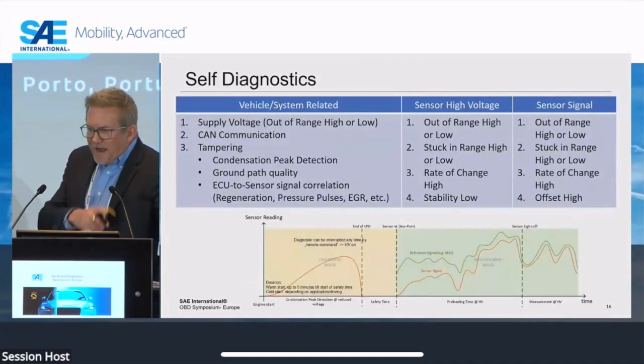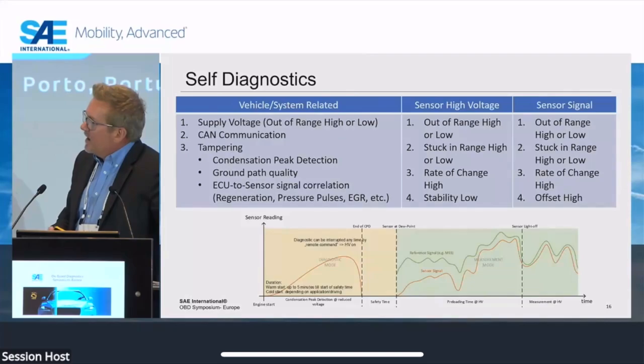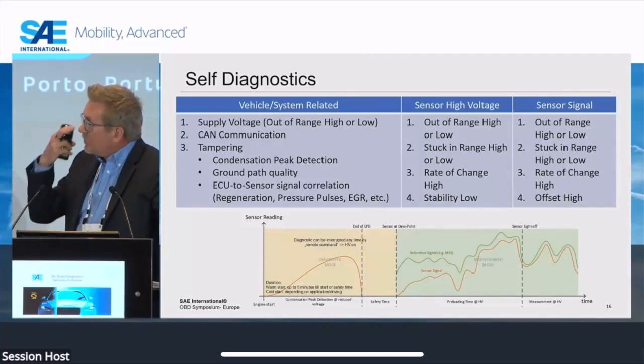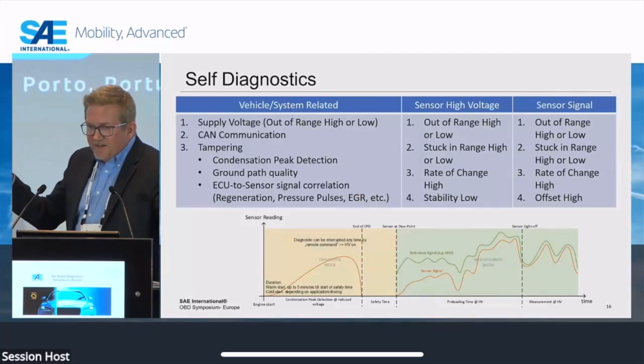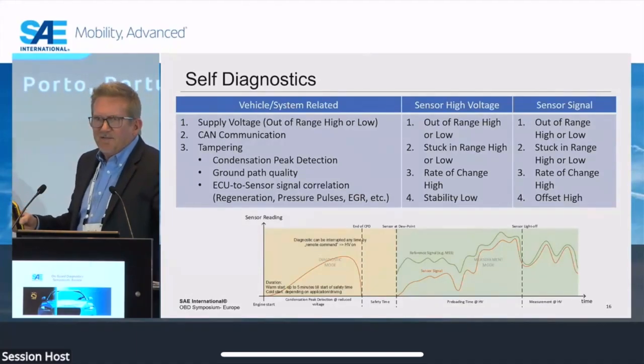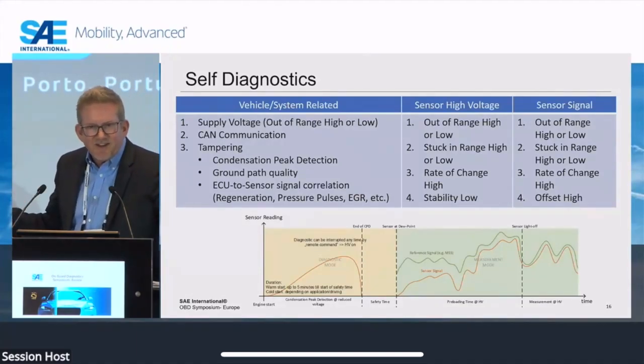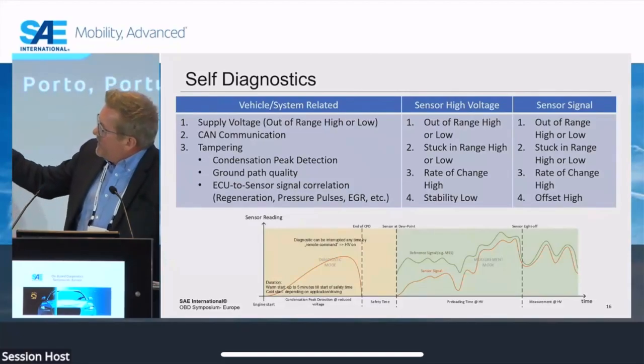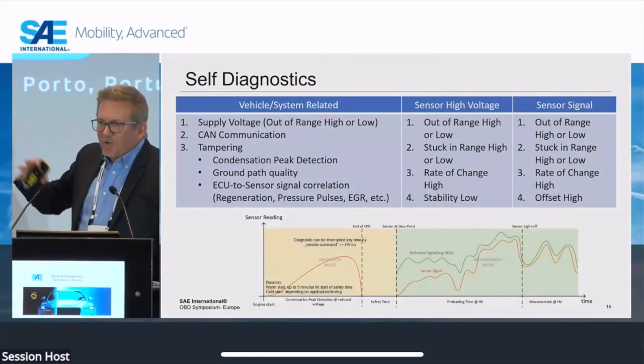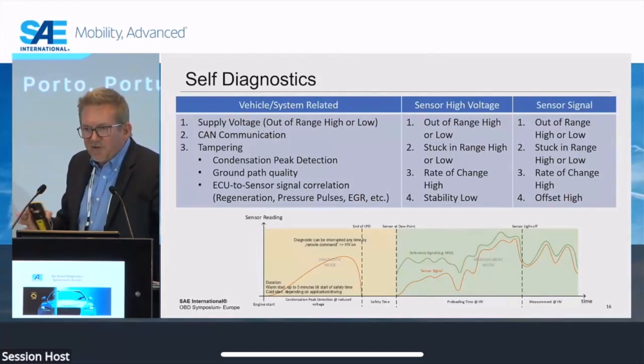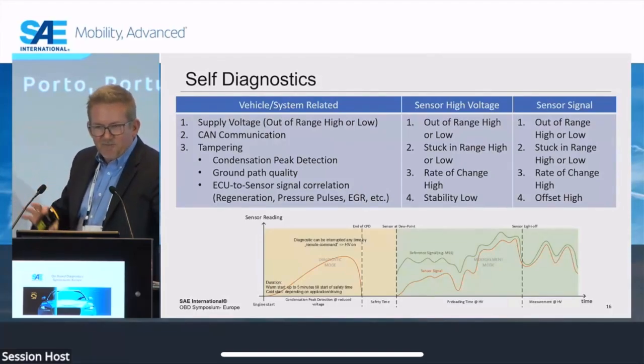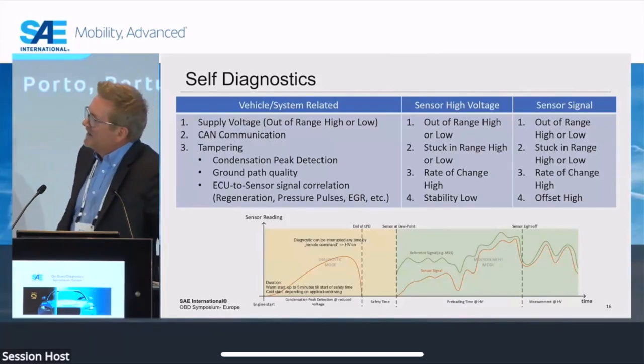Before I wrap up the sensitivity topic, I wanted to touch on sensor self-diagnostics for a second. The sensor diagnostics are really similar to most OBD sensors. You're looking at things like out of range high or low, stability, or rate of change. If the rate of change is higher than it should be, then you question the plausibility.